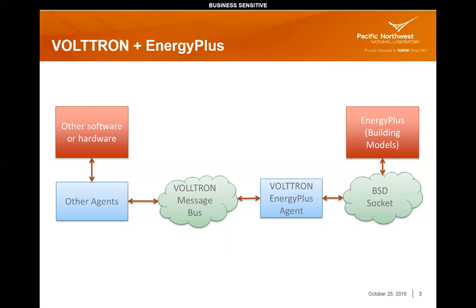And then from another agent, you can send commands which try to override the set point or building system. It can be done in two different ways. The first way is that the EnergyPlus agent subscribes to certain messages. Once you publish a certain control action to a certain message, it triggers the EnergyPlus agent to override, for example, the set point or a low level control action inside EnergyPlus. Then you can see how the building operation is affected by the updated control.